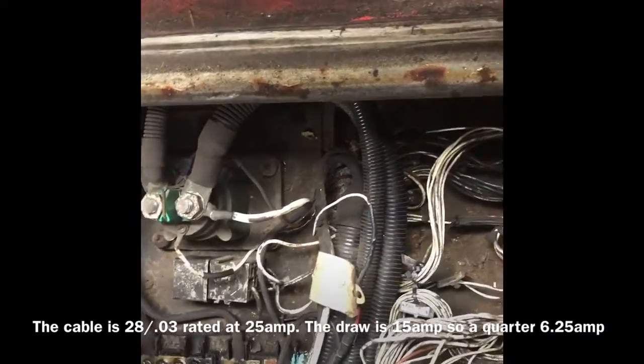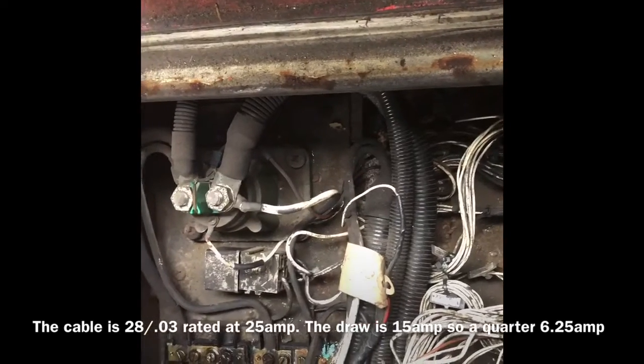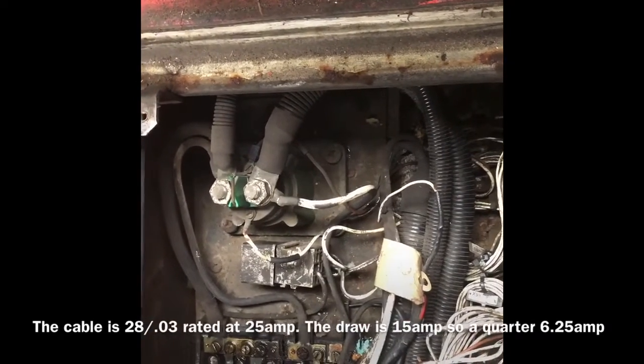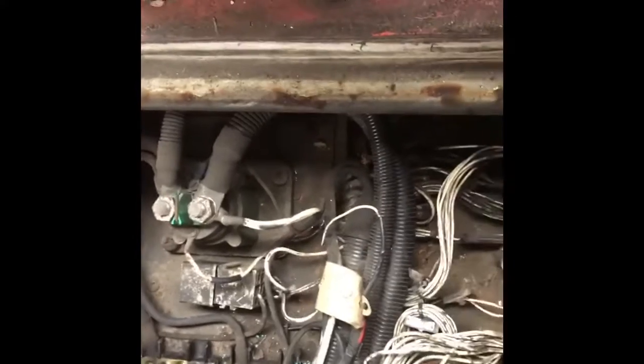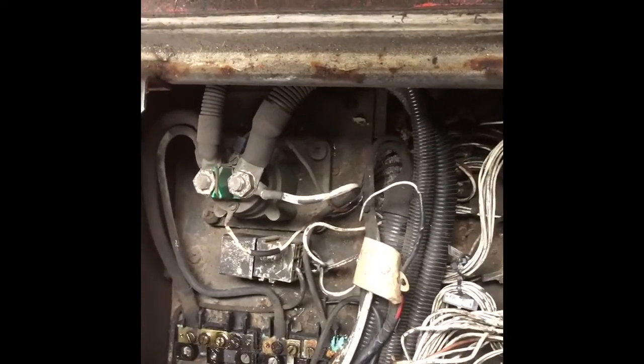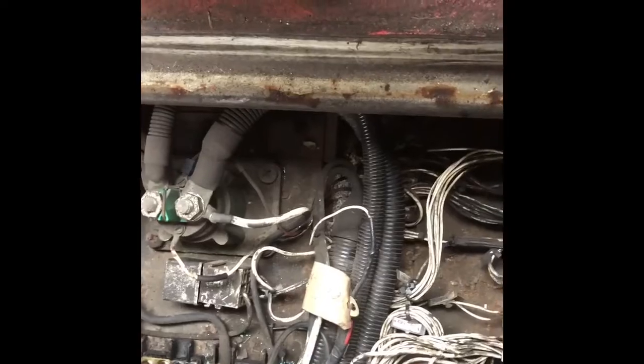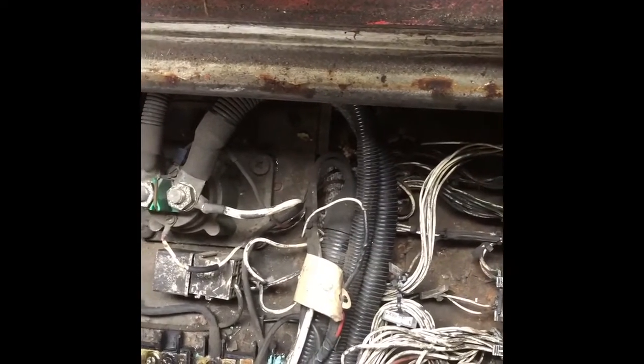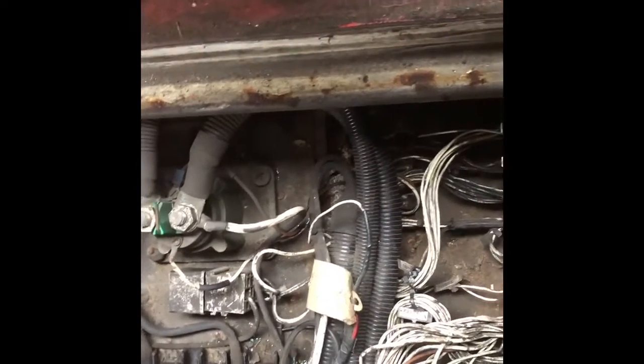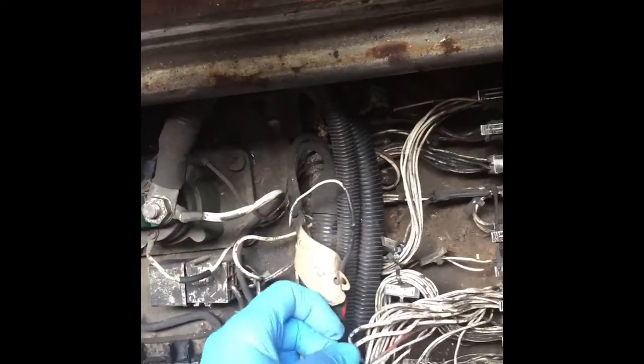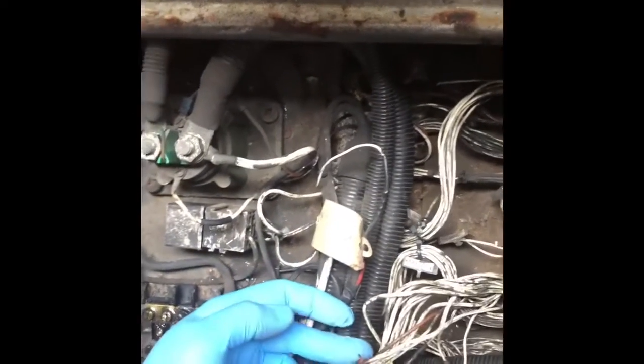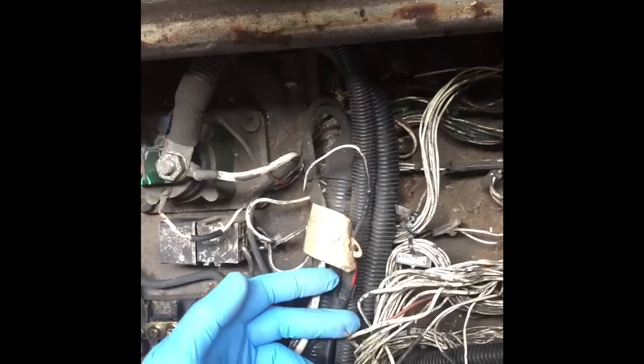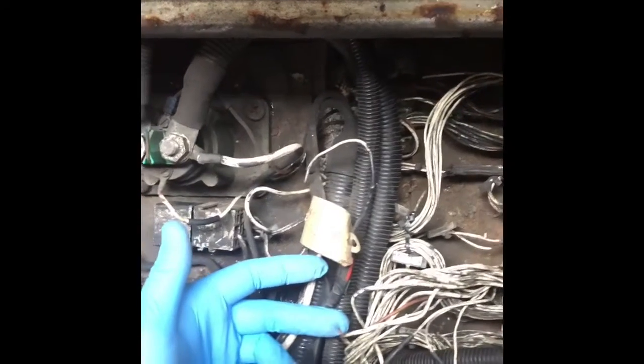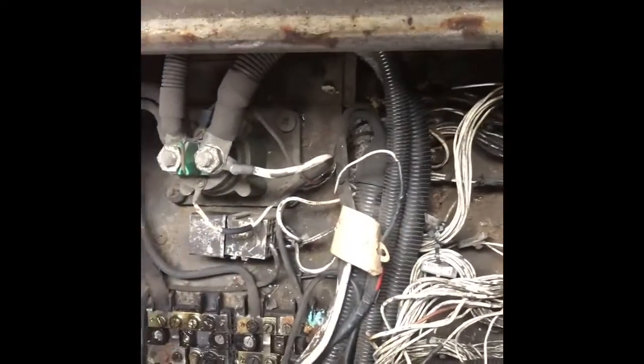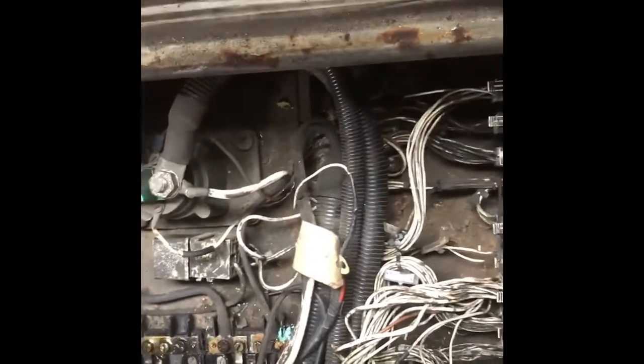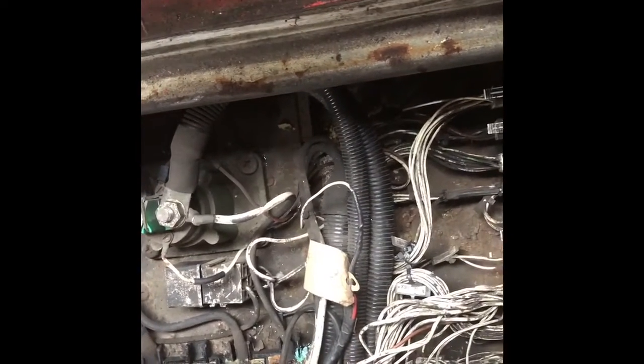So what you'd actually want to do when you finish doing your repair, when you fix the plug at the front, is power up this cable with its original loads on it, and then put the load probe on it, so you're actually testing the real draw on this cable, because this cable is like 28 strand. So with it loaded, you'd probably see it rear its ugly head, but because we're just testing from point A to point B, it doesn't give us an effective result.